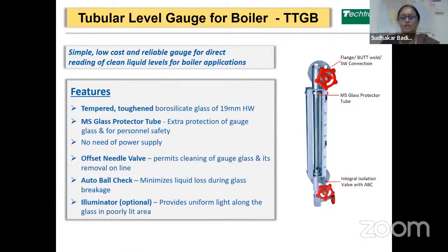This is a simple, low cost and very reliable gauge for direct indication of clear liquids, which can be used in boiler applications. So basically, when this is mounted on the side of the tank, you can see the liquid level through the glass. This glass is tempered and toughened borosilicate glass of 19 mm diameter, heavy wall. And this is protected with an MS glass protector tube, with the C channel already provided for its protection.